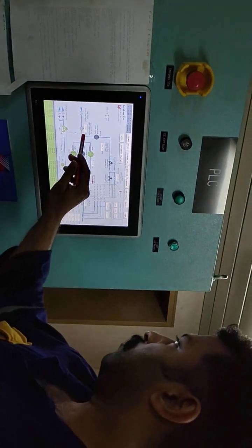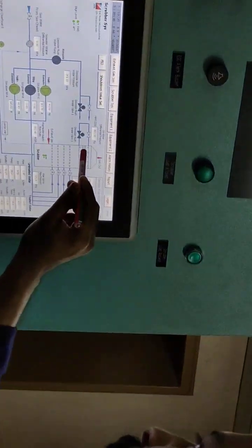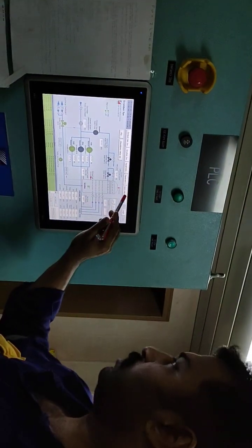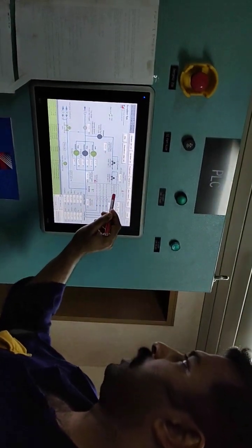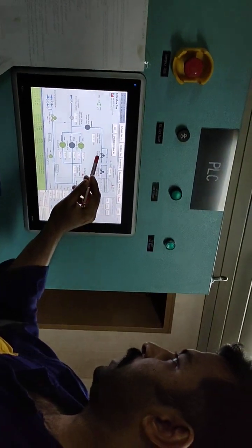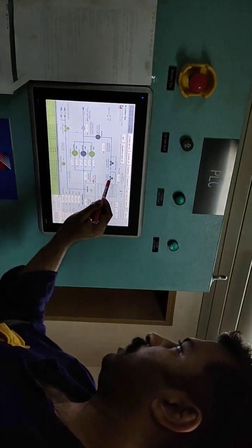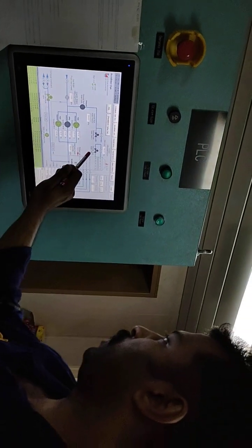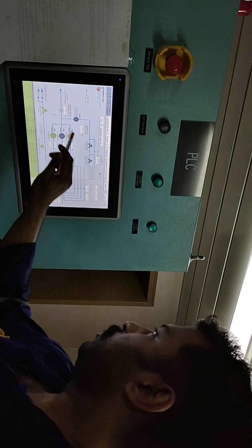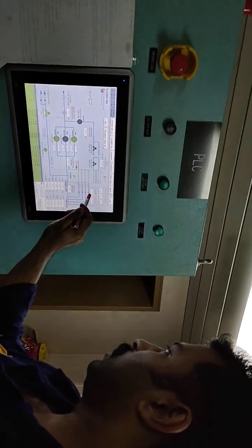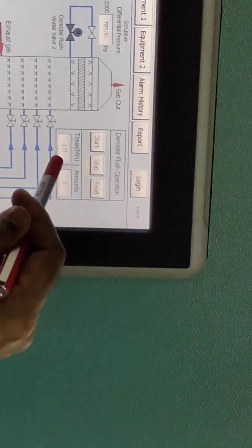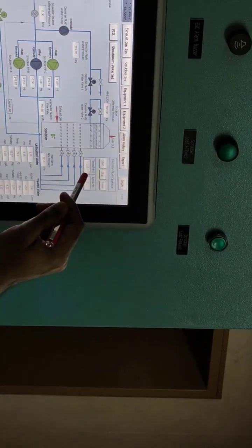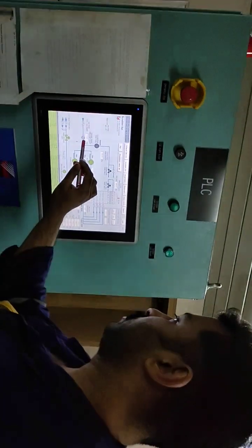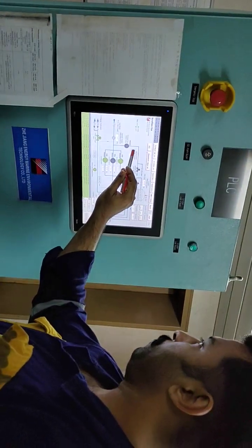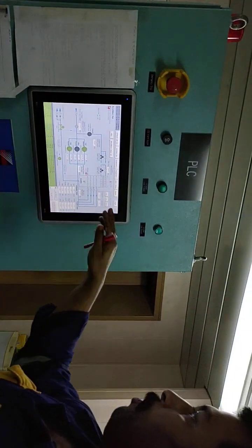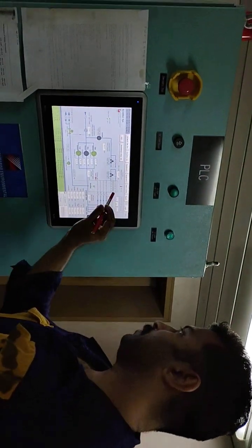This area is finished, and from here on the top we have a demister arrangement. It is just to filter the dirt and moisture going up. This demister needs to be cleaned regularly. How is it getting cleaned? There are two items. One is the manual valve and the other one is the demister flush valve. Valve number 1 and valve number 2. This is automatic, so it has a timer. Now the timer is 1 minute. For 1 minute in a day it will run and then automatically stop. The pump will take suction from this line, this demister water pump, and it will spray on top and bottom of the demister so that the demister gets completely cleaned.